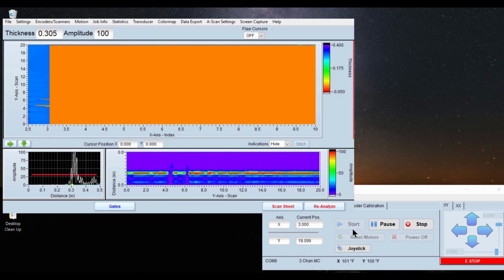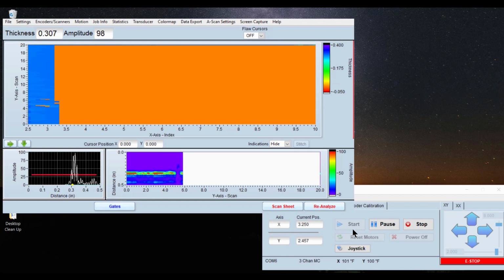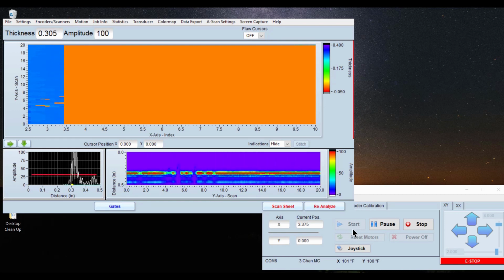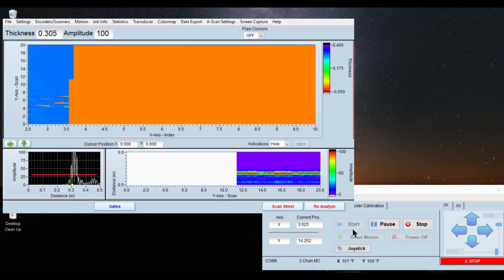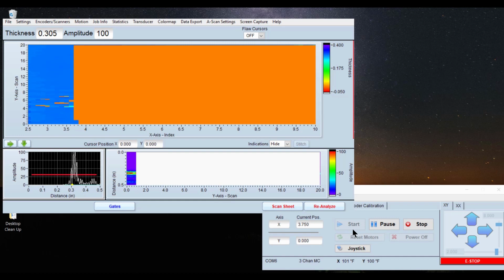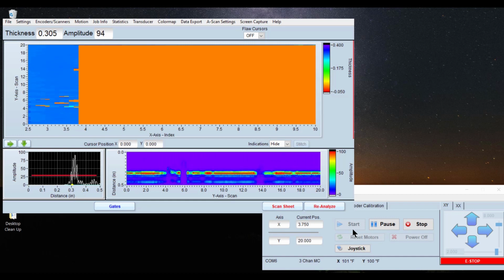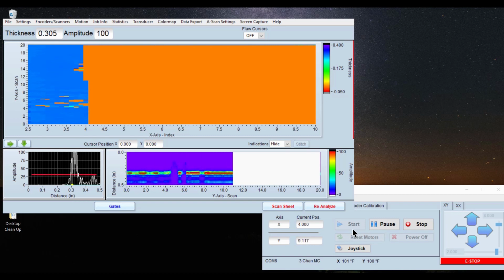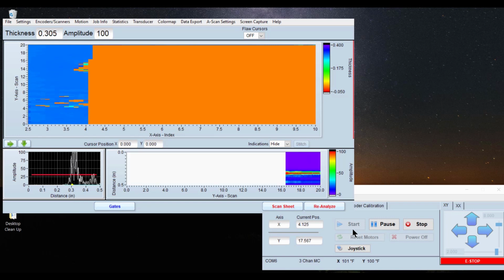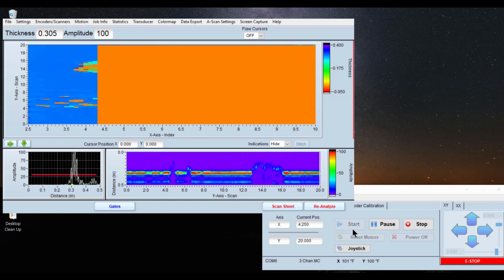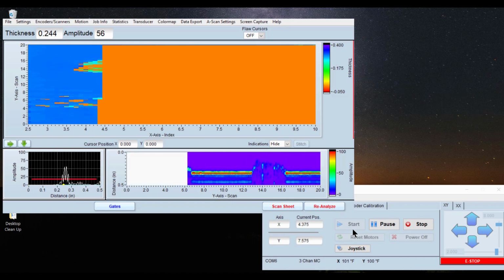Now you'll start to notice we're actually picking up a little bit more detail around the edge of those indications. Looks like we have the start of some general pitting, and this will also allow for better analysis when it comes to characterizing the patterns that you're seeing. Whereas that looked like general corrosion before, it looks like it's just isolated general pitting. And now we're starting to come into the second flaw. Looks like it's some general corrosion.